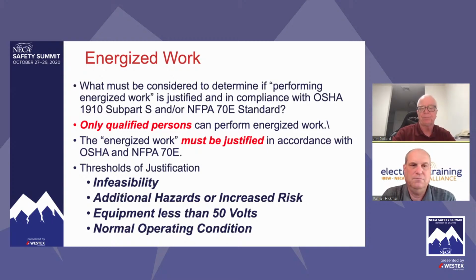It's obviously not maintained, and as Palmer pointed out, the incident energy is directly proportional to the time. So if you get 300% of the clearing time, going from 6 cycles to 18 cycles, you've got 300% of your energy.